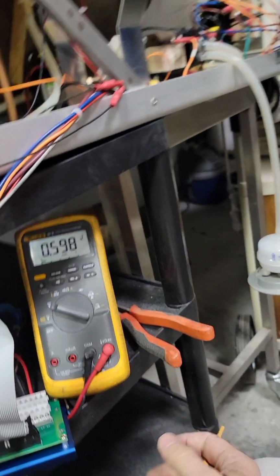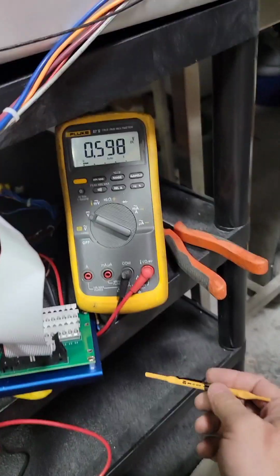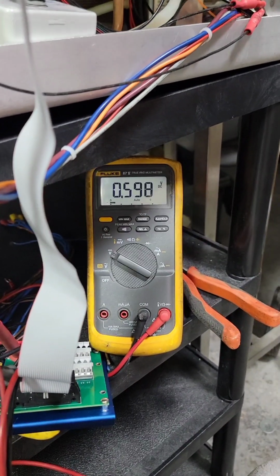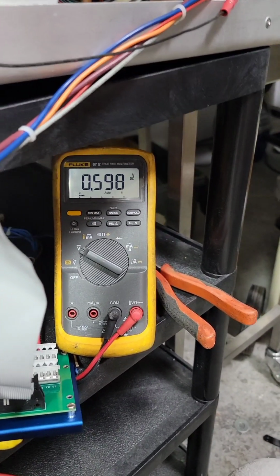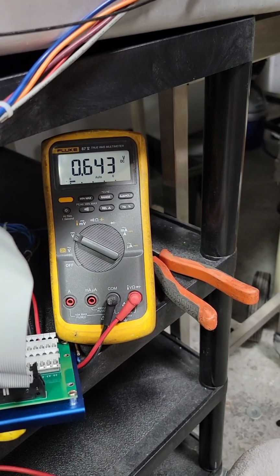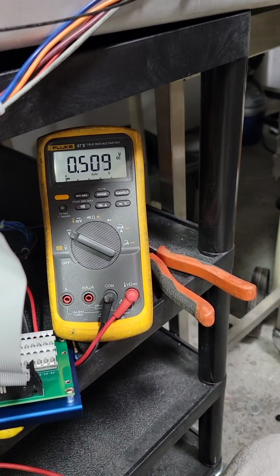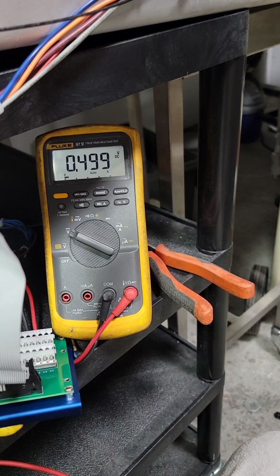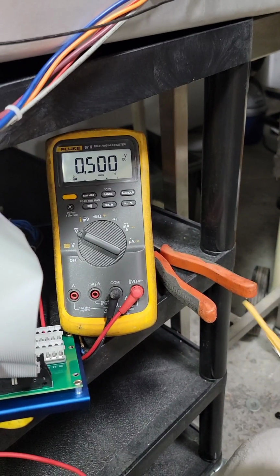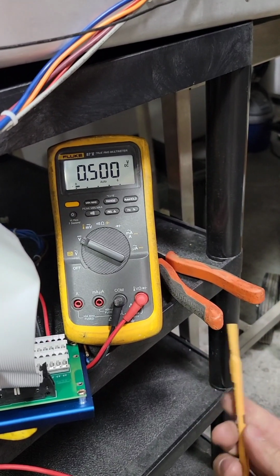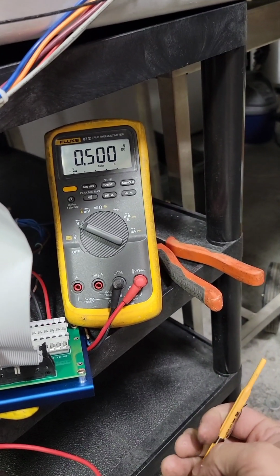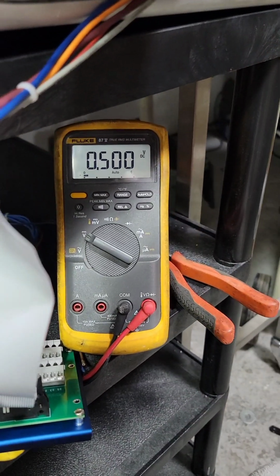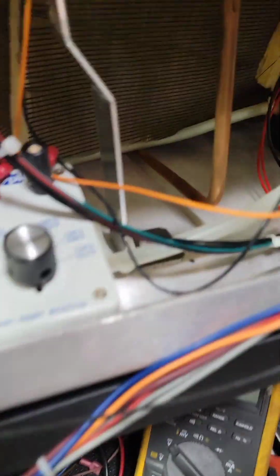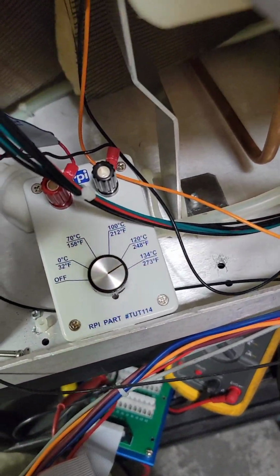Anyway, I just went through the calibration again. We'll just start with pressure instead of temperature. So right now we're at 598. It's too high. Remember, we want to be at 500 millivolts. So let's go clockwise to go down. And there we are. Boom! And it's holding. We're already doing way better than last time. Next up, let's go. Temperature calibration backwards, 273 we'll start with.